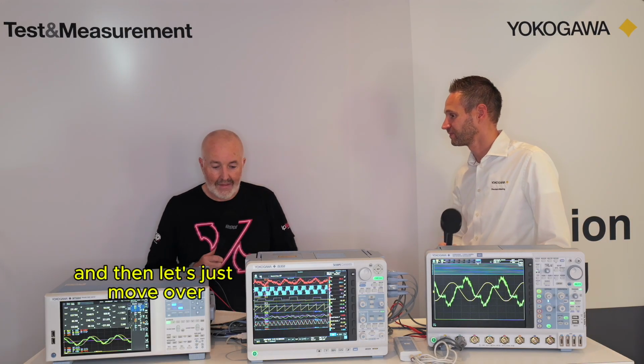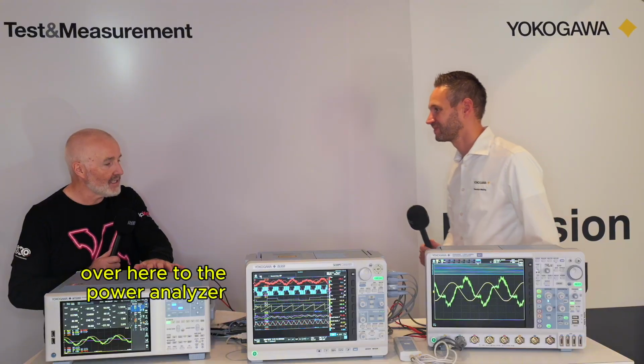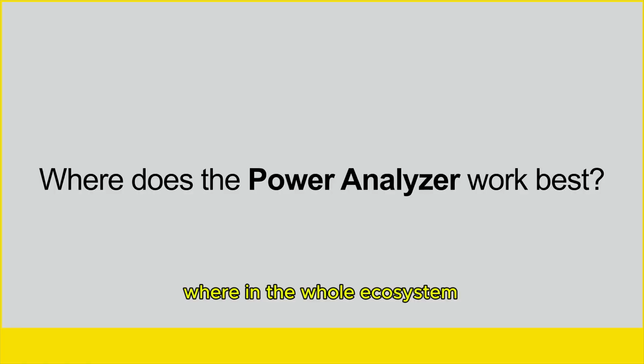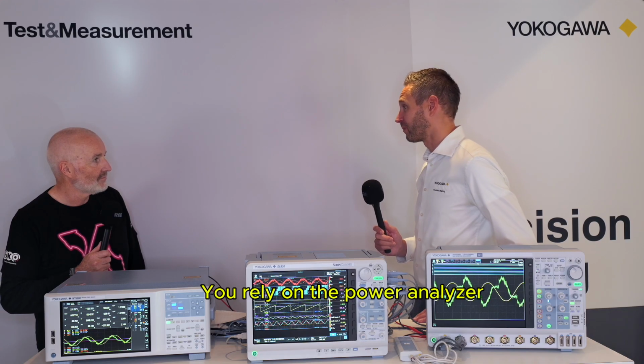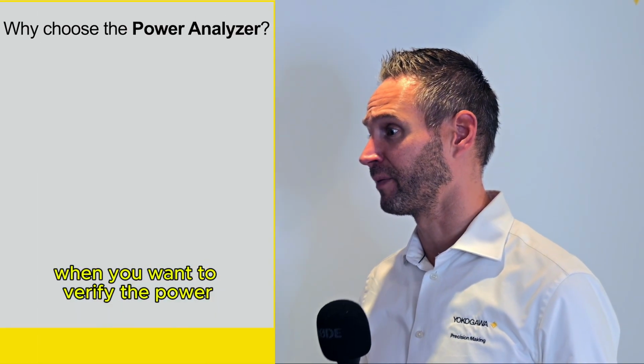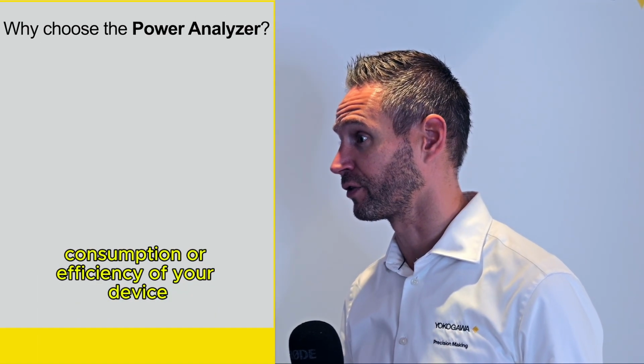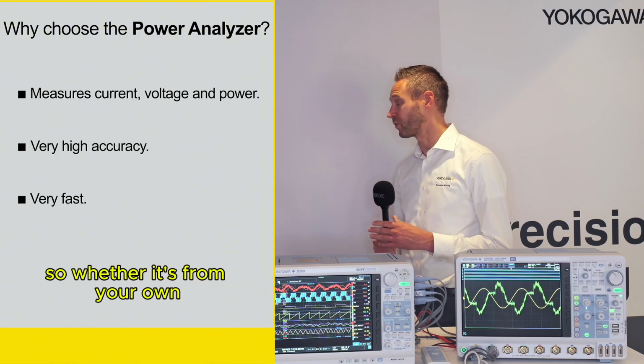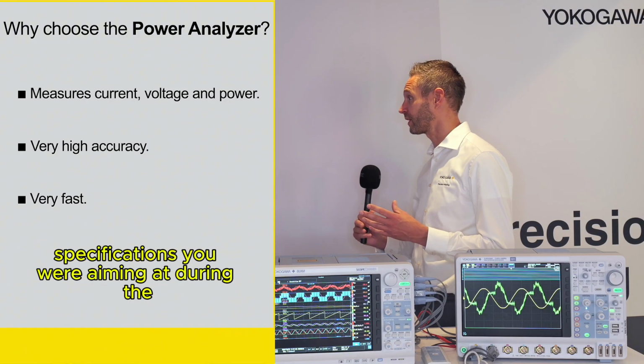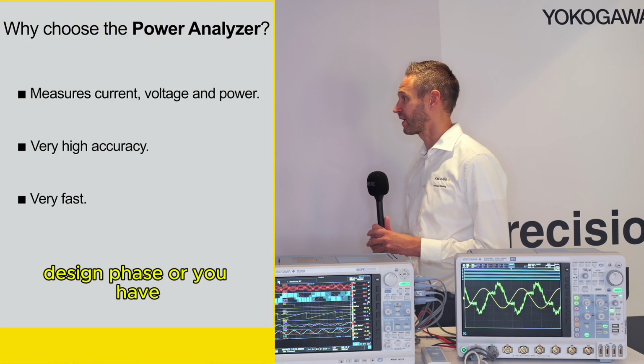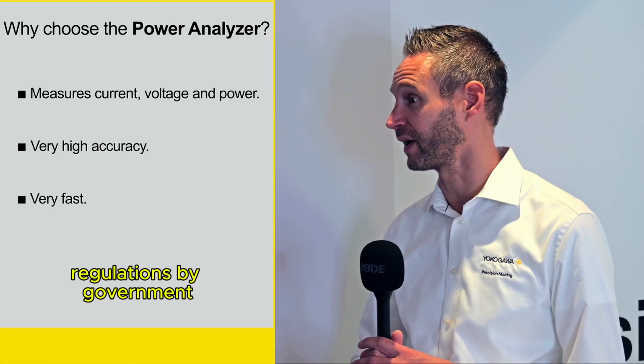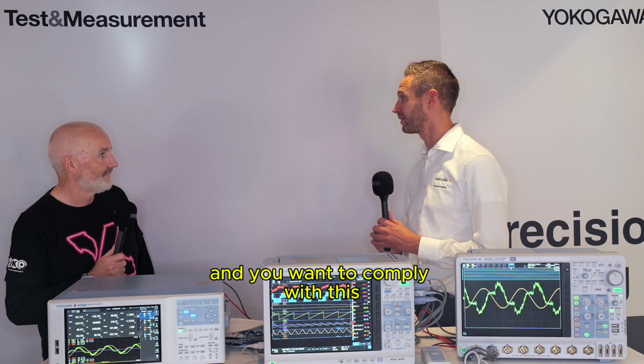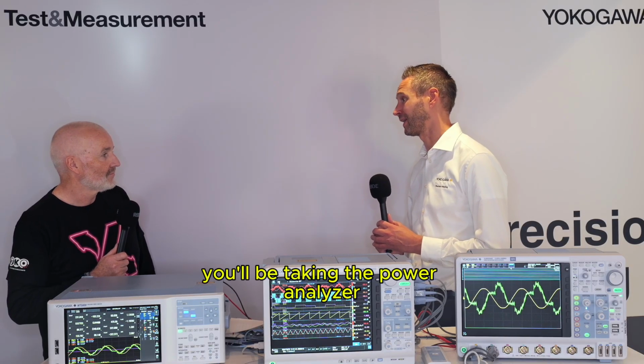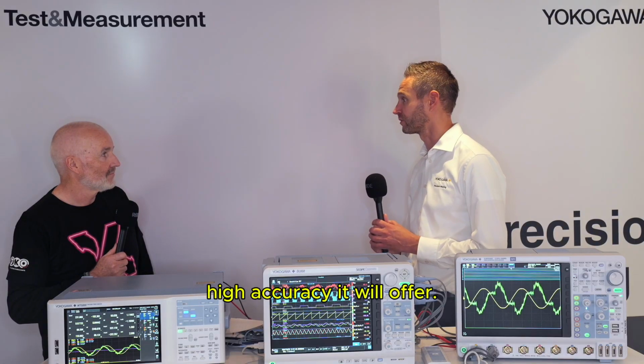Excellent. Okay, good. And then let's just move over here to the power analyzer. Where in the whole ecosystem of things does it do its best work? Yeah, so you will rely on the power analyzer when you want to verify the power consumption or efficiency of your device. So whether it's from your own specifications you were aiming at during the design phase, or you have regulations by governmental bodies, when you want to comply with these, you will be taking the power analyzer and you will benefit from the high accuracy it will offer.